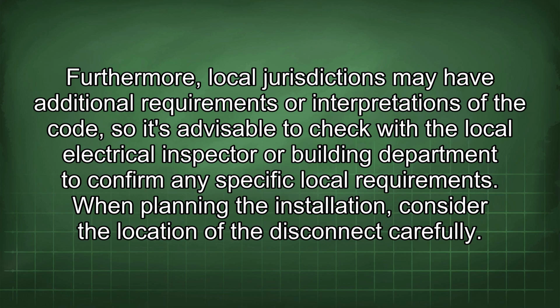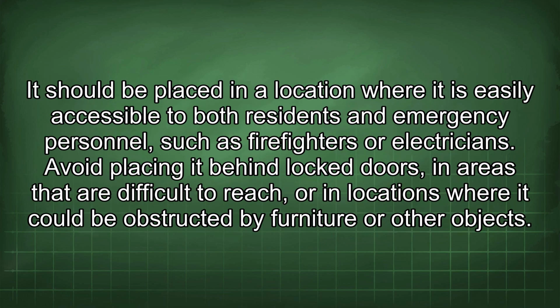Furthermore, local jurisdictions may have additional requirements or interpretations of the code, so it's advisable to check with a local electrical inspector or building department to confirm any specific local requirements. When planning the installation, consider the location of the disconnect carefully. It should be placed in a location where it is easily accessible to both residents and emergency personnel such as firefighters or electricians. Avoid placing it behind locked doors, in areas that are difficult to reach, or in locations where it could be obstructed by furniture or other objects.